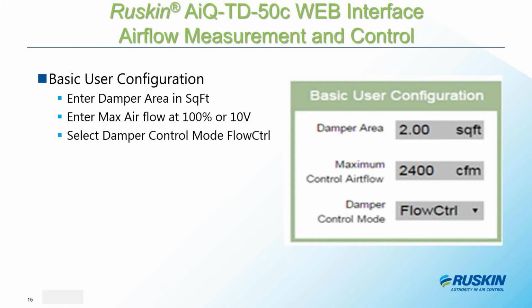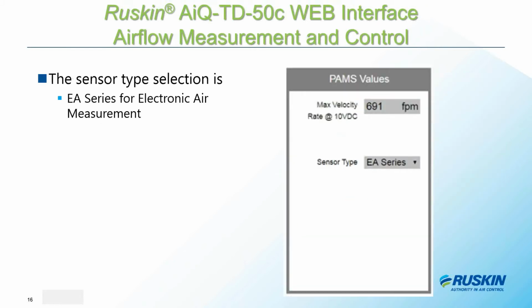But if you've reconfigured the TD-50c and set it so that the max airflow that you expect is closer to 1,200 feet a minute, then your max airflow would be 2,400 CFM. That's just simply 2 times 1,200 feet a minute. So again, you'll get a lot better air measurement resolution by changing it from the factory default. But again, totally welcome to leave it at the factory default as well. So pretty easy in terms of how that goes.